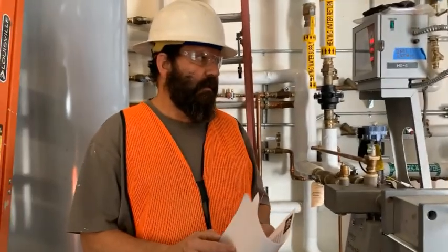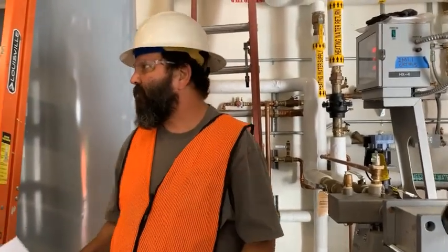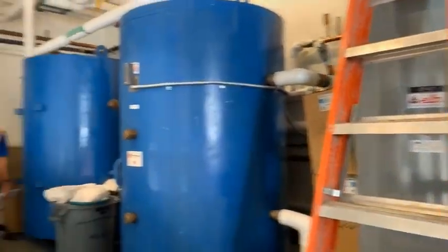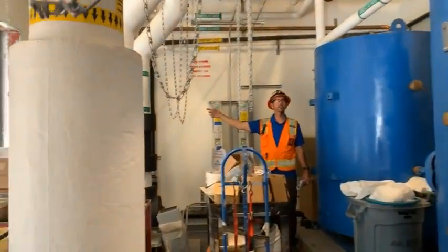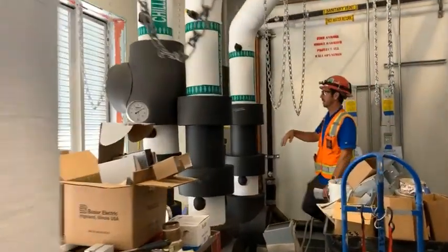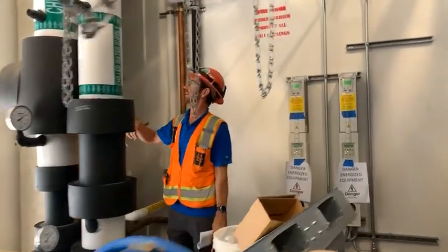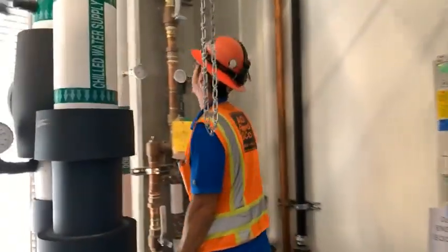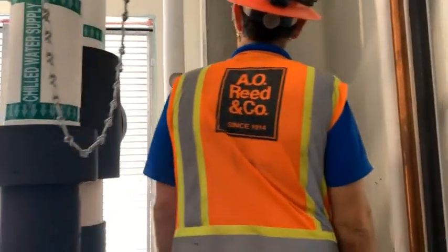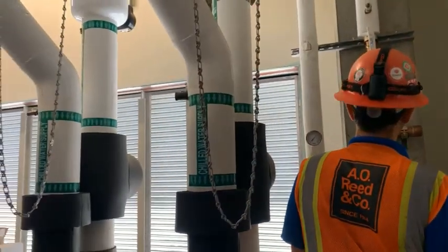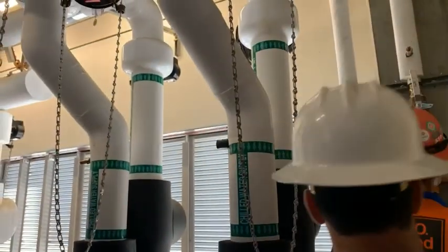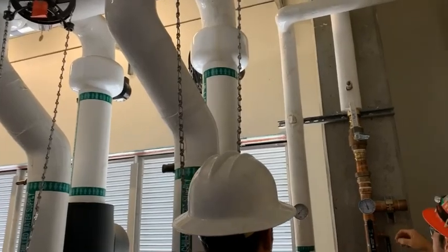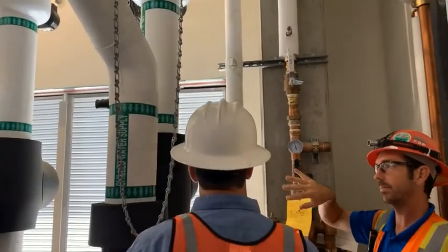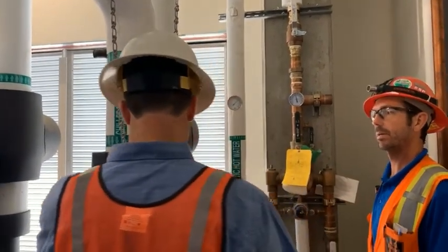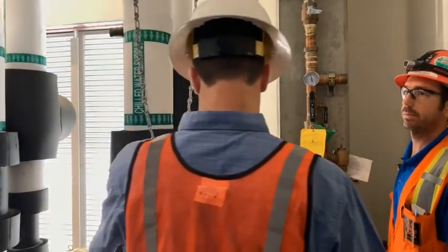So right now, until this thing gets back online, we're gonna be chasing our tail because we have a thermometer over here. The water coming into the valve is only like 132. I don't know what happened. We just had a spike. We're right back at 120. So it had a little dip. They might have had some weird usage in there, or just momentarily it went down to that lower number.